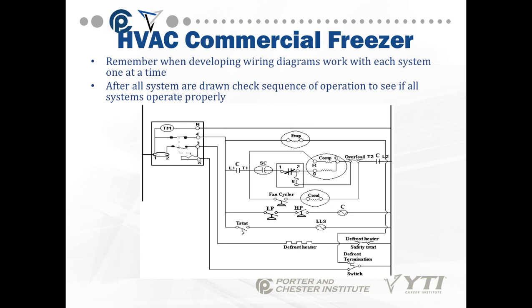When developing wiring diagrams, work with each system one at a time — don't try to do everything at once. Start with the line, add the defrost clock, then add each system one at a time. After all systems are drawn, check the sequence of operation to see if all systems operate properly. Being able to draw schematics and understand schematic diagrams is the difference between a great technician and a mechanic. Refer back to these diagrams over the course so you can see the different configurations, and keep these as good references once you get into the field.